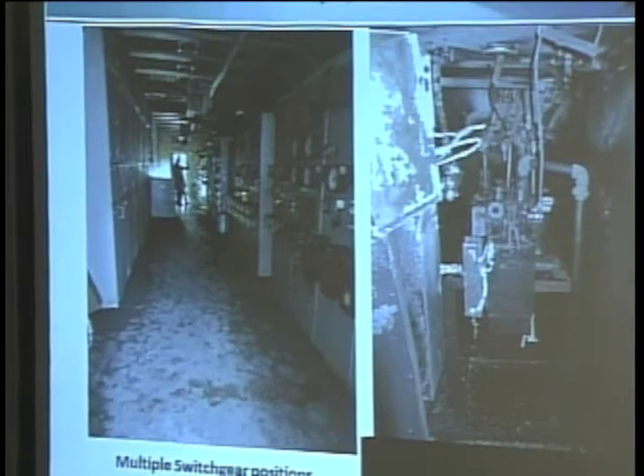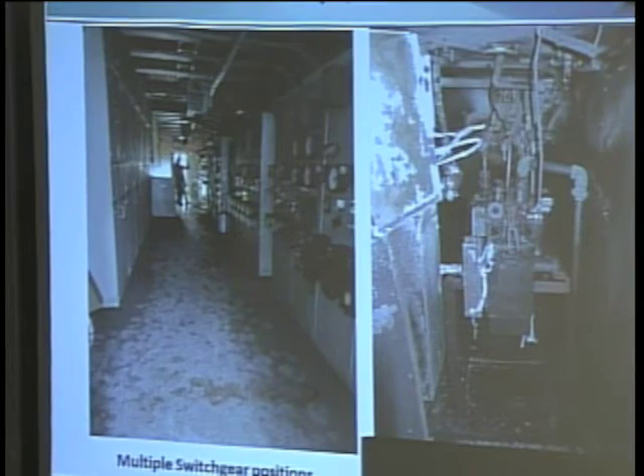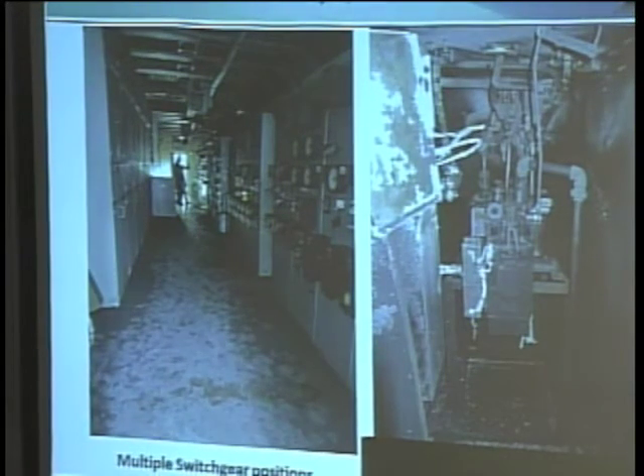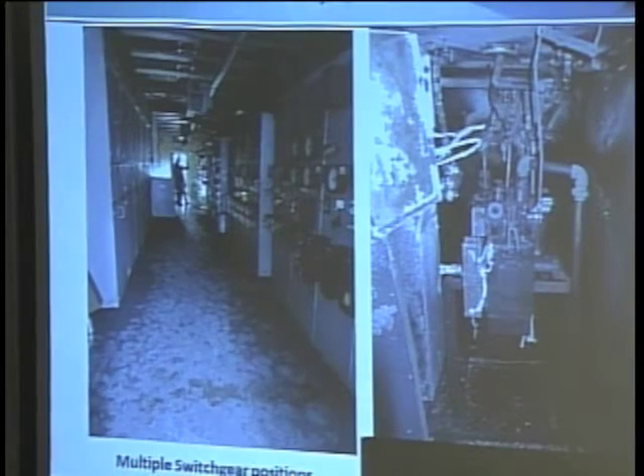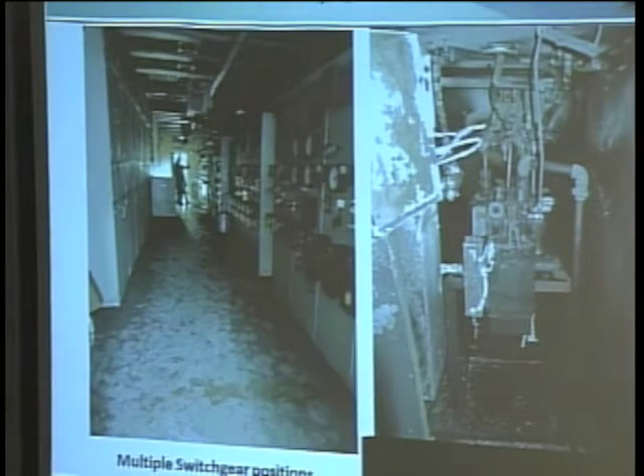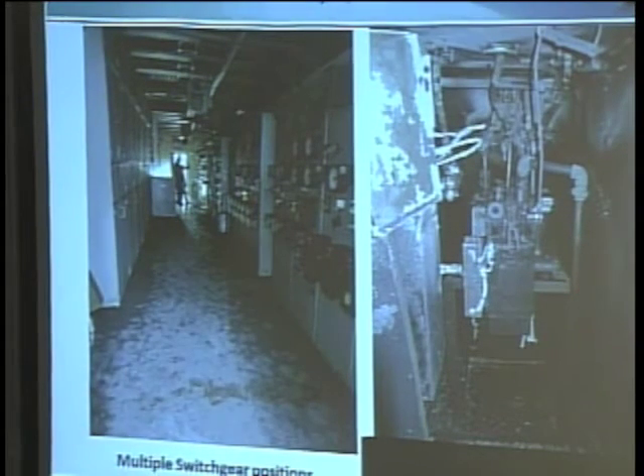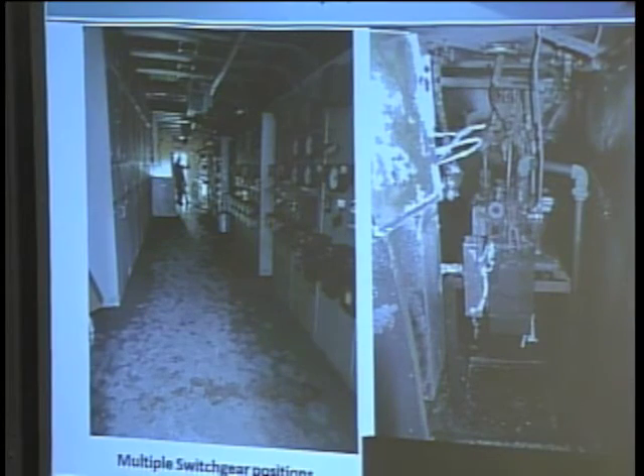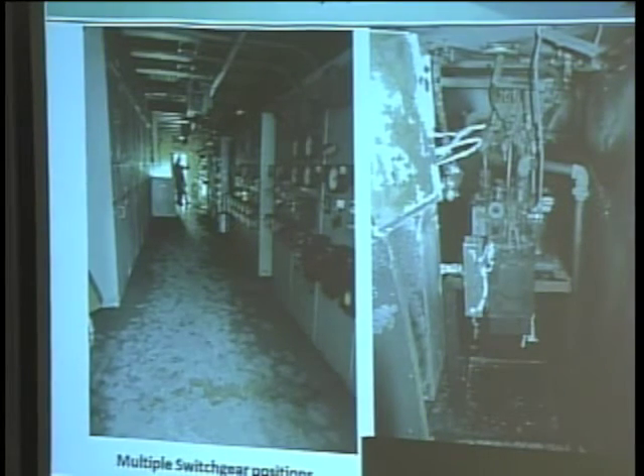But the areas here on the position that's damaged, we had to redo the cables, and then they have to purchase new breakers, and they are going to rebuild that. But what we did temporarily was to transfer some of the load over to adjacent circuits that had the capacity.